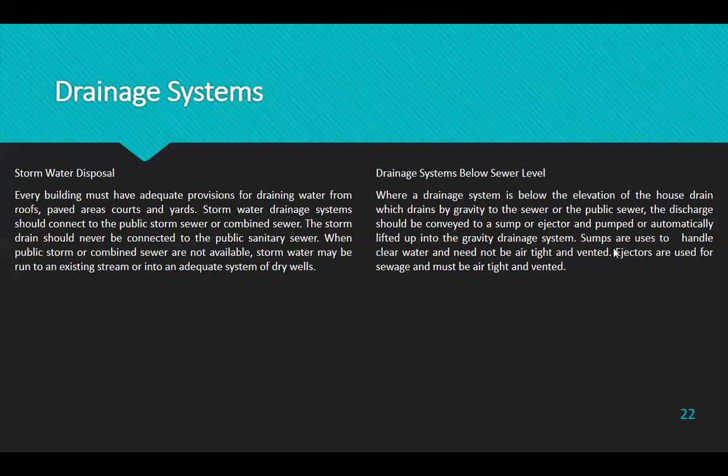Sumps are used to handle clear water and need not be airtight and vented. Ejectors are used for sewage and must be airtight and vented.